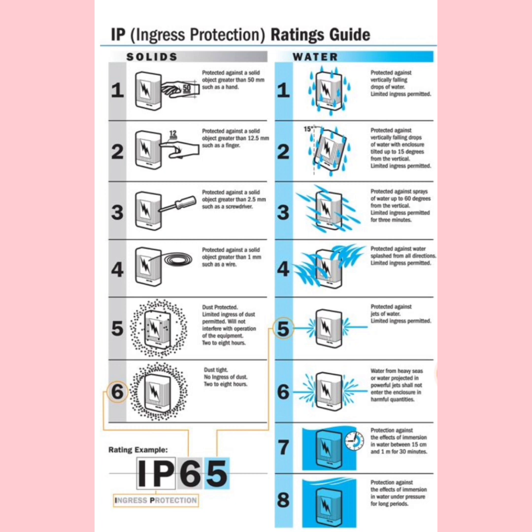For example, if you have purchased one enclosure that shows IP65 — if you look at the first number, six means it is dust tight. For the second number, five means it can withstand a jet of water without failure and without affecting the function of the equipment.